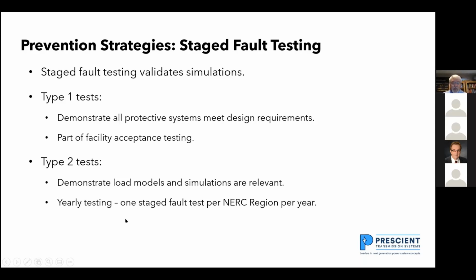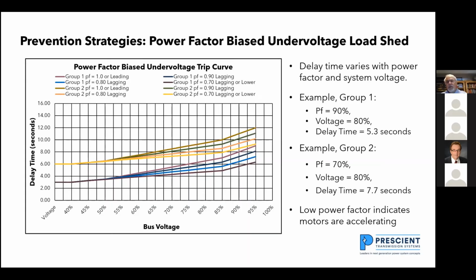So I'm thinking we should do one yearly staged fault test per ERCOT region per year. So this is in addition to staged fault tests we do every time we add a new facility. And this would prove that all the calculations and all the simulations we've done are relevant and appropriate. And another thing we want to see put on is power factor biased under voltage load shedding.